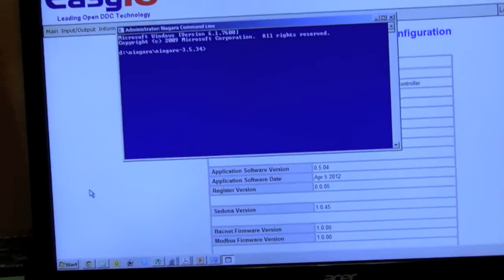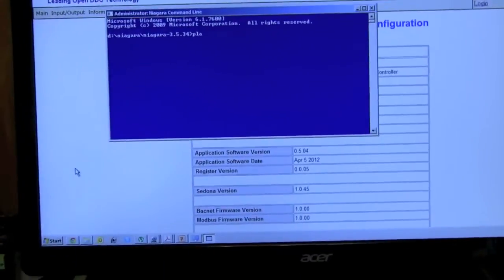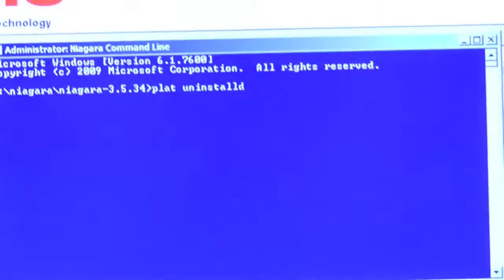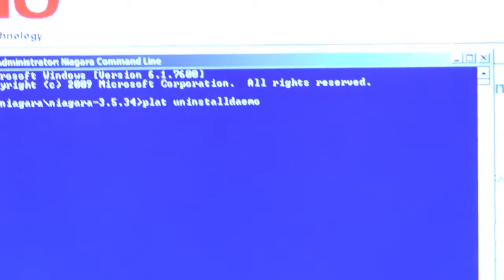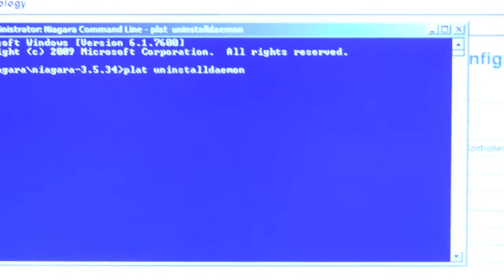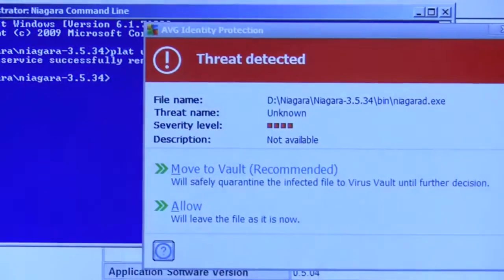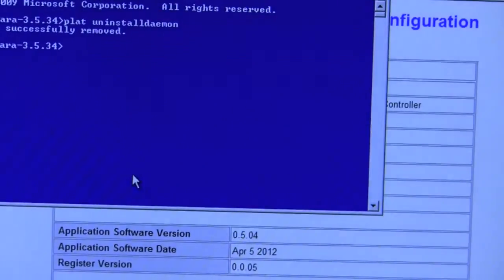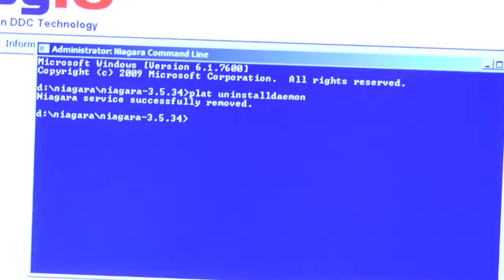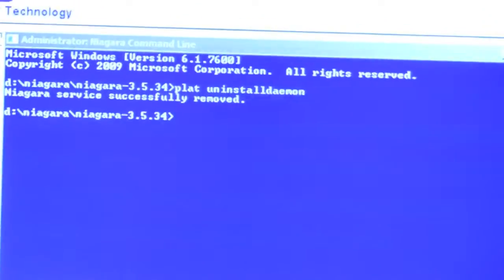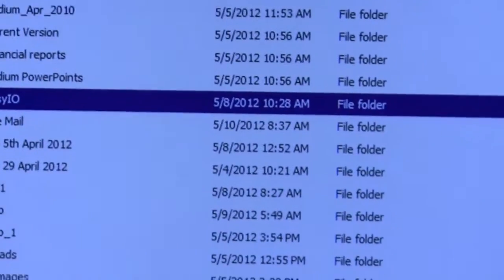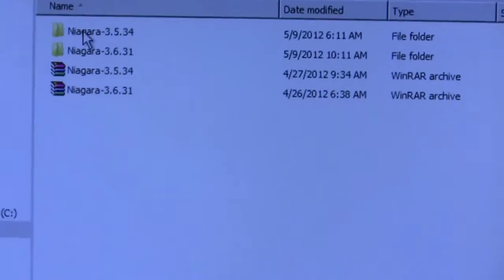And type in plat uninstall daemon. And sometimes you will get an antivirus but don't worry about that. And it did say it was successfully removed. That will now allow me to change things in my Niagara directory without it telling me that I can't do so.